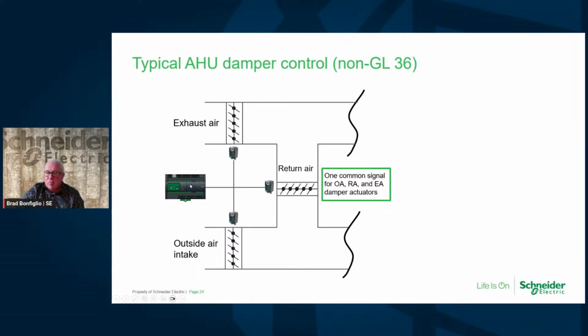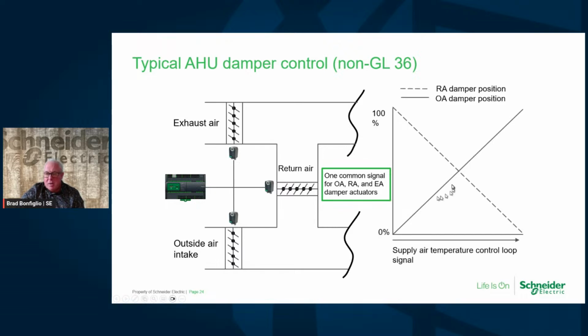You've run out of IO points. Whatever the case, it happens more than you think. And when you control like this, the differential pressure across your mixing box looks like this, because you're assuming they're all proportional in nature.